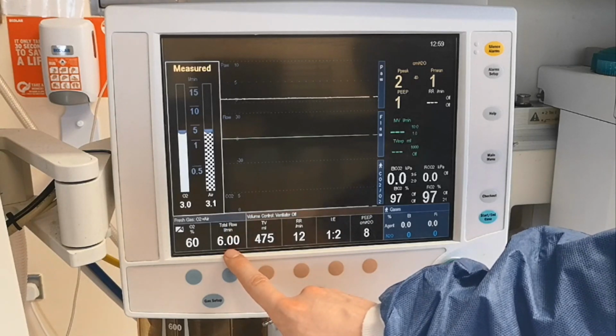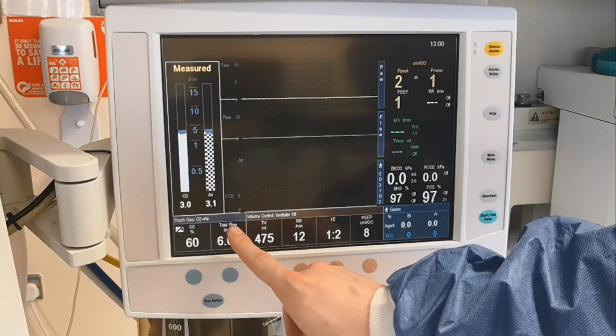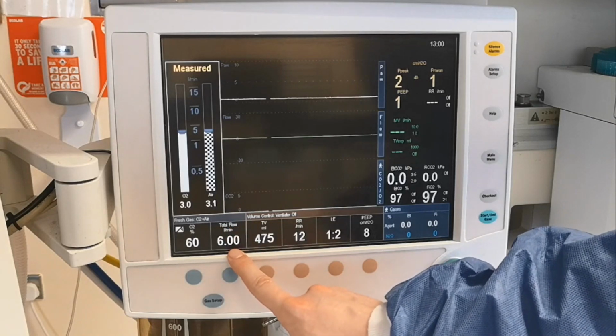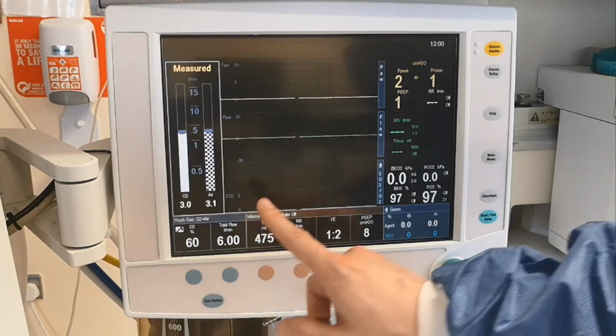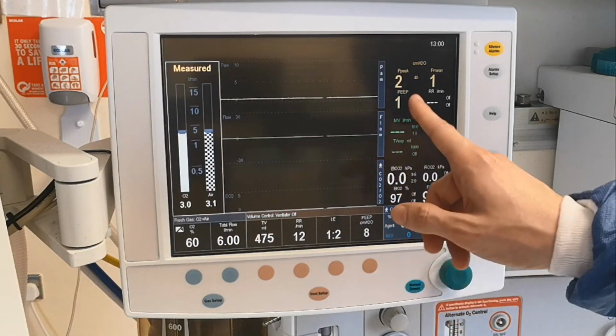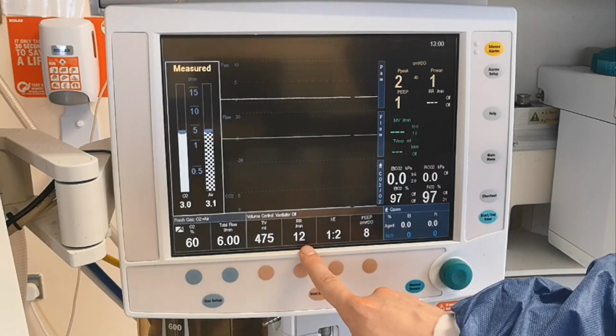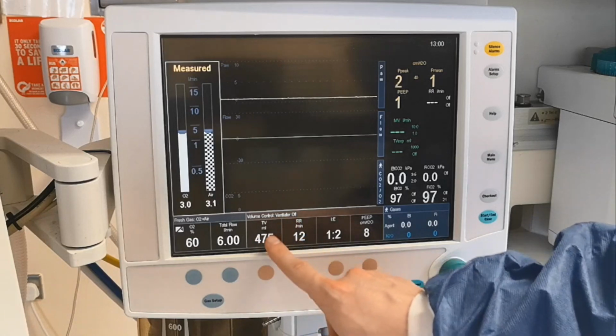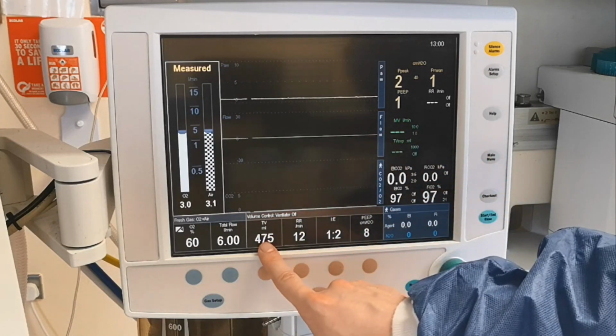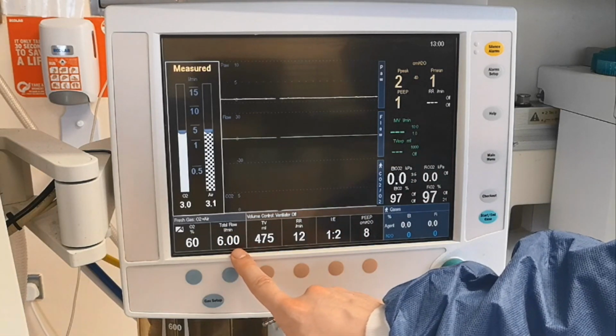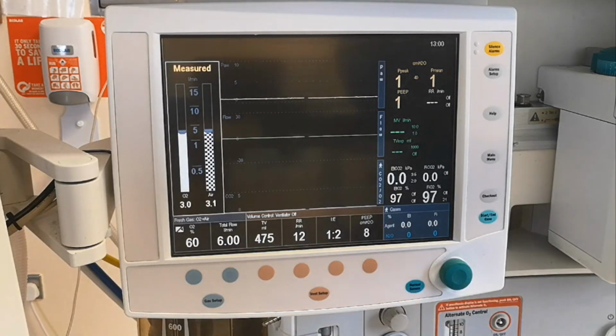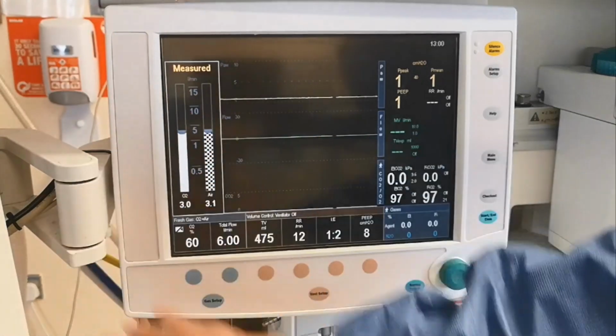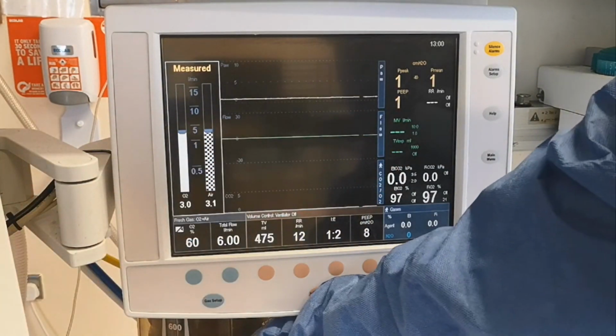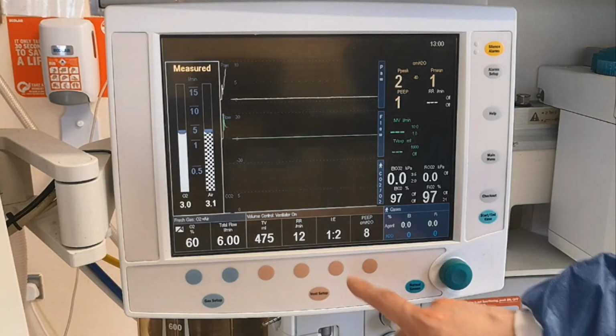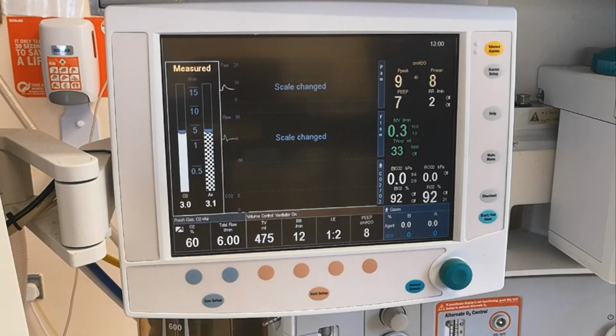Long story short, if you have a fresh gas flow higher than the minute volume of the patient, and the minute volume is the tidal volume multiplied by the respiratory rate, so if this number, the minute volume, is smaller than the total flow of gas, that means the patient is always breathing fresh air and oxygen coming from the wall. Let's try to switch on the ventilator. So I just go down here and flip the switch to the ventilation mode and see what happens. Okay.